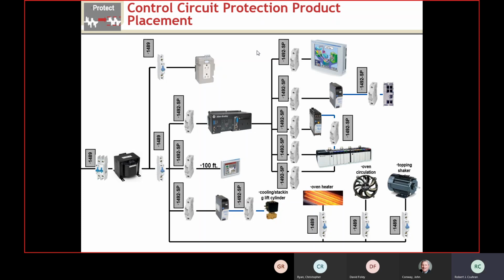I've had customers tell me a UL inspector denied the 1492, saying it was done incorrectly. I've even had inspectors question it and ask for all 1489 units, sometimes because they lack the knowledge, or maybe they're just covering themselves. So some customers buy 1489 across the board for two reasons: they don't want installers to install the wrong product, and they don't want to run into issues with a UL inspector, because it doesn't matter if you're right if it prevents the startup of a machine and leads to arguing back and forth.